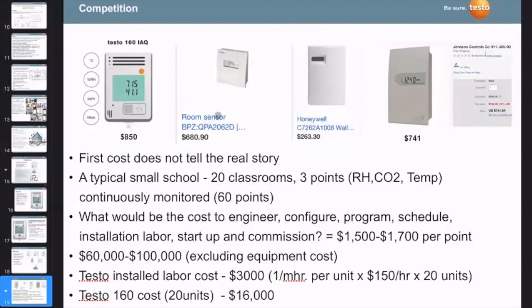A typical temperature control contractor needs to cover the cost of the engineering time to design the system, to configure it, to program these additional points into the existing system in that building space, schedule it, install it, start up, and commission. Typical cost across the country on average is about $1,500 to $1,700 per point of information. So yes, per point for RH, CO2, and temperature, and that's excluding the cost of the devices themselves. If we multiply these numbers times 60 points, you're going to be running close to 6 figures just to implement the labor component of putting sensing technology in 20 classrooms.